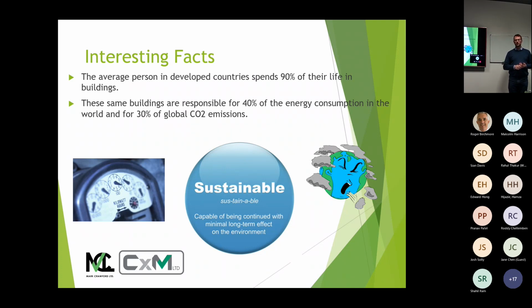30% is low-hanging fruit. It's fixing simultaneous heating and cooling issues. It's fixing sensors in the wrong place that are being influenced by photocopiers that are driving your VAV plant down to minimums and creating extra energy use. It's having areas that are running air conditioning when they're not occupied and the like. So real simple, low-hanging fruit stuff.